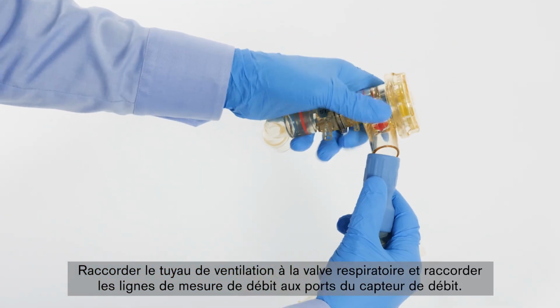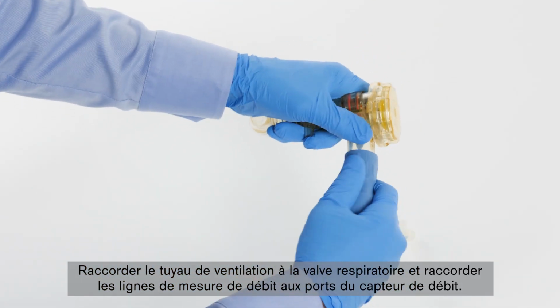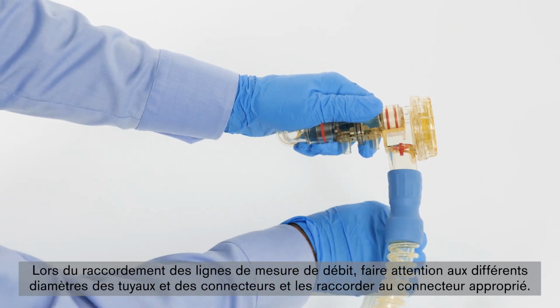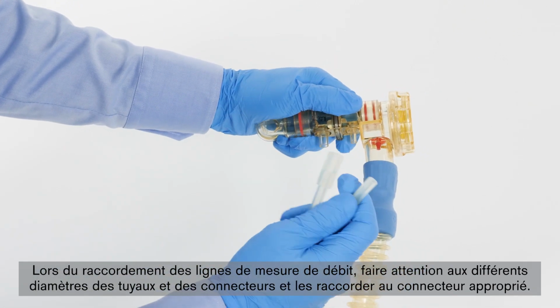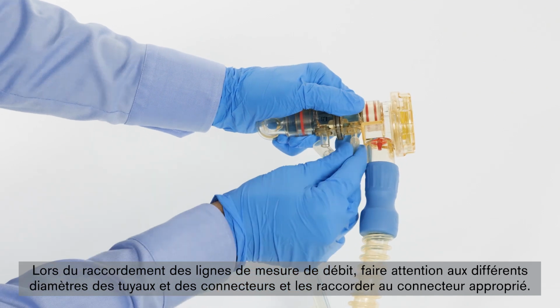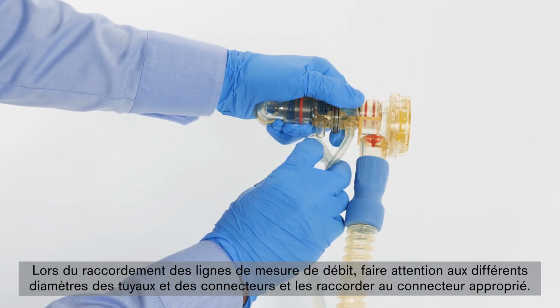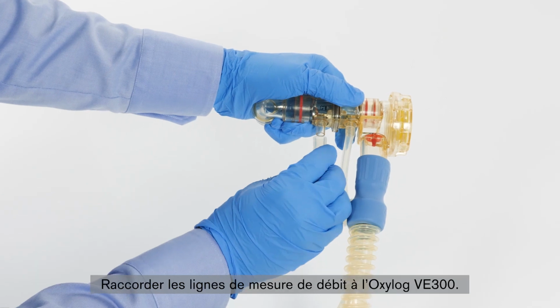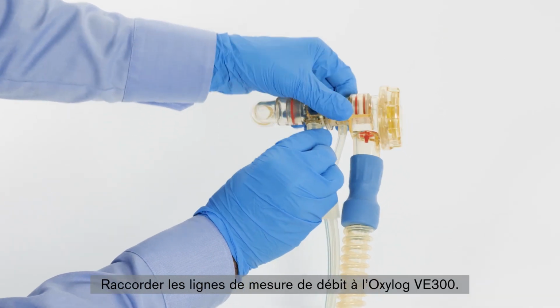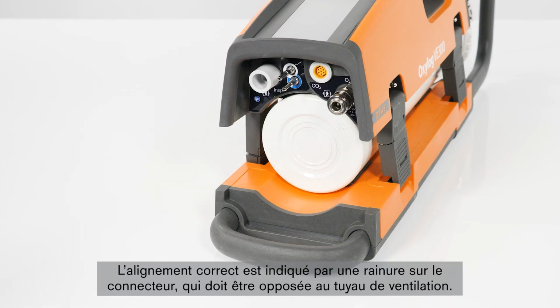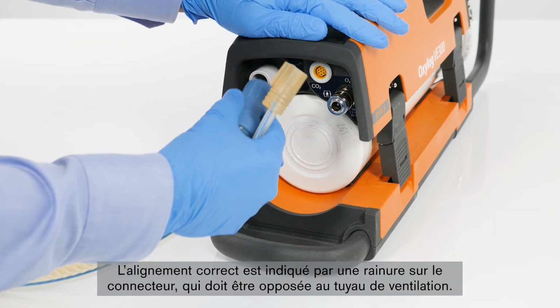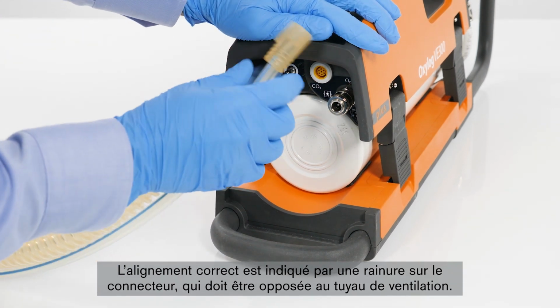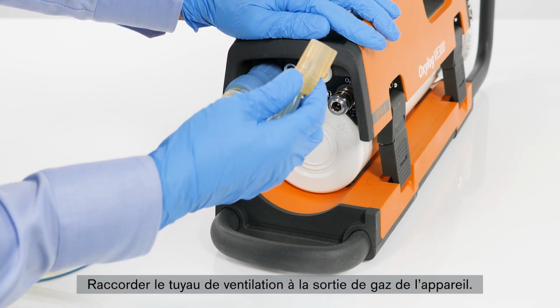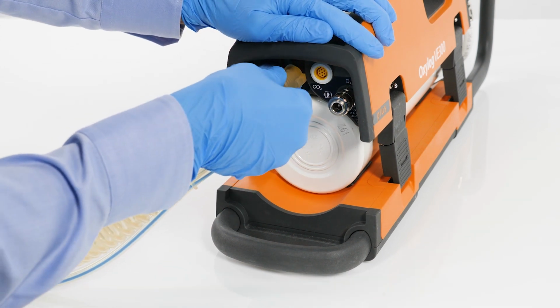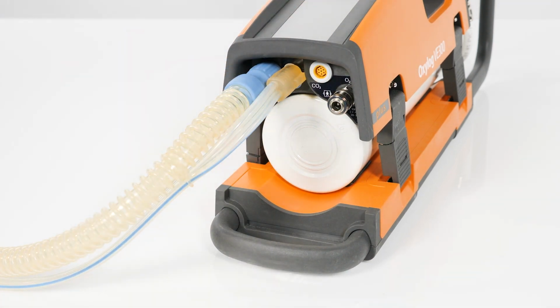Connect the breathing hose to the breathing valve and connect the flow measuring lines to the ports of the flow sensor. When connecting the flow measuring lines, pay attention to the differing diameters of the hoses and connectors and connect them to the correct connector. Connect the flow measuring lines to the Oxylog VE300. Correct alignment is indicated by a groove on the connector, which must point away from the breathing hose. Connect the breathing hose to the device's gas outlet.